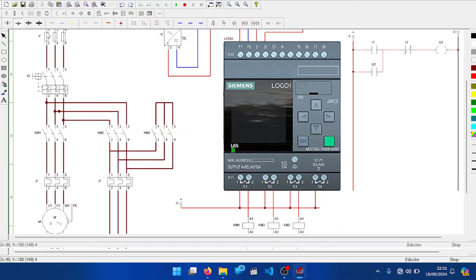So you must have the logic right. In order to reduce the inrush current, it is always advisable to start our induction motors in star configuration before switching to delta configuration. So I'll use a typical value of 10 seconds. Your motor will be in star configuration for 10 seconds. Then after that, it will switch to delta. So we need a timer, an on delay timer. Then we set that timer for 10 seconds. So after 10 seconds, it will switch to delta. So let's do that.